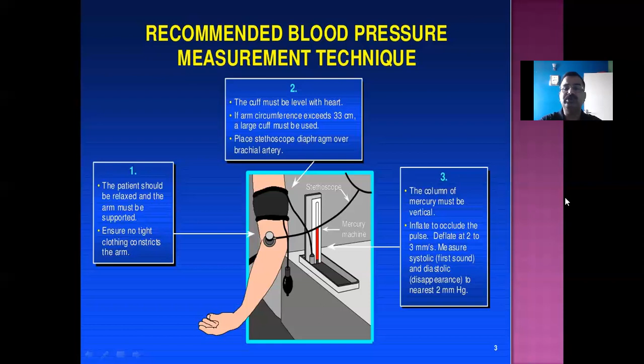So the cuff must be at the level of the heart. We have already told that the size of the cuff should be first selected as per the arm circumference. Then place the stethoscope diaphragm over the brachial artery. Then the mercury column should be placed vertically. We should first inflate the balloon to occlude the pulse over the radial artery and deflate it slowly. Inflate somewhat fast, but deflate slowly, at say 2 to 3 millimeter of mercury per second. Measure the systolic first sound and diastolic disappearance of sound nearest to 2 millimeter of mercury. So we have to always take the even number, not the odd number.